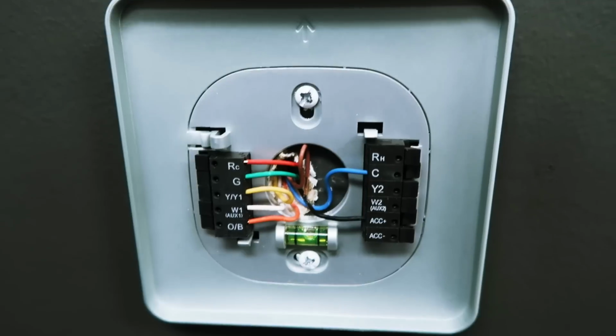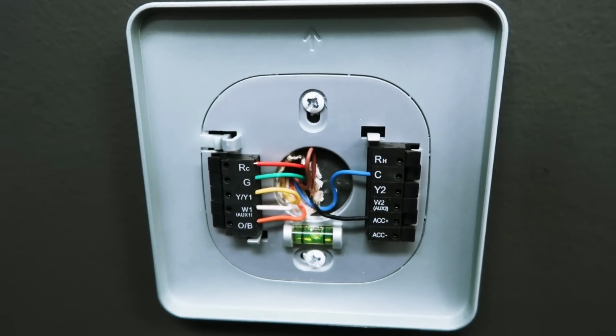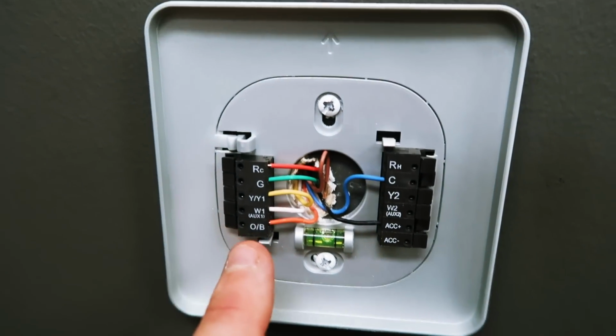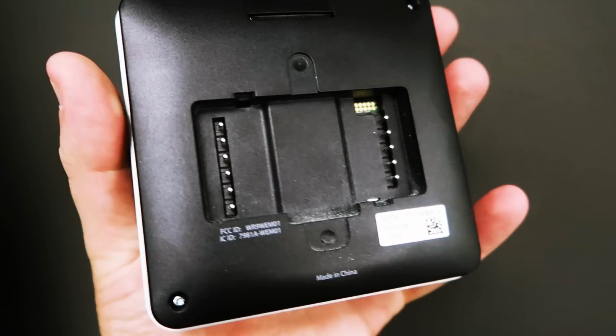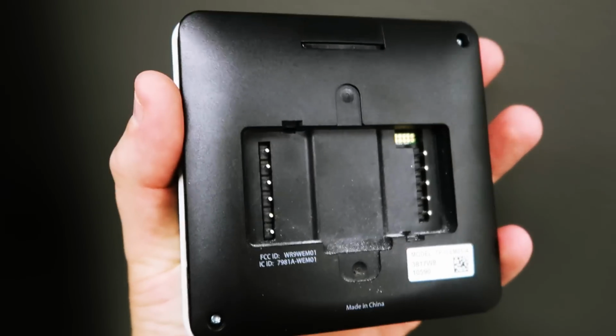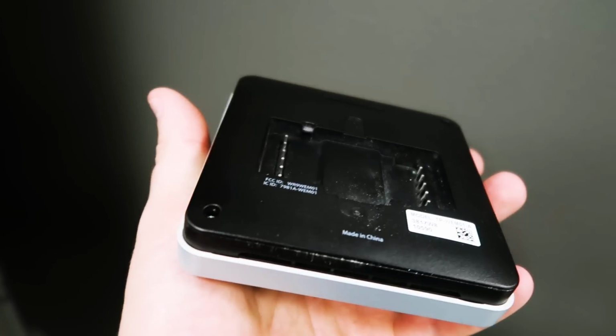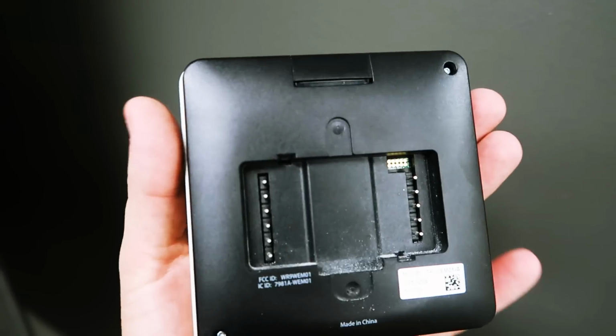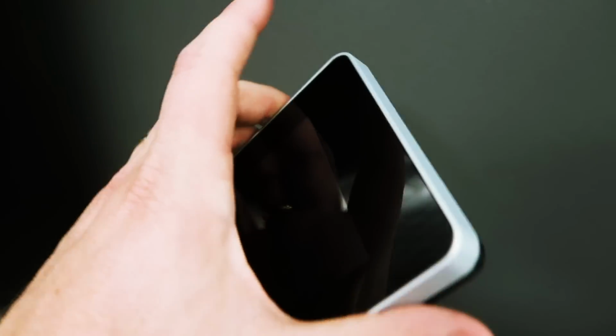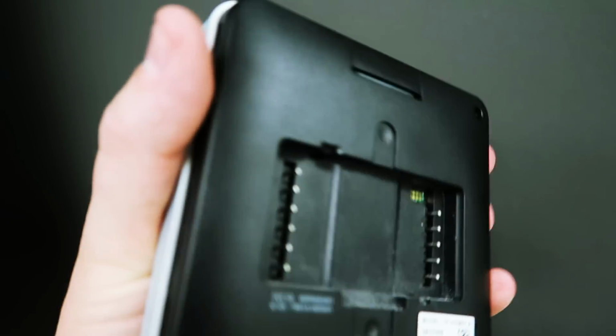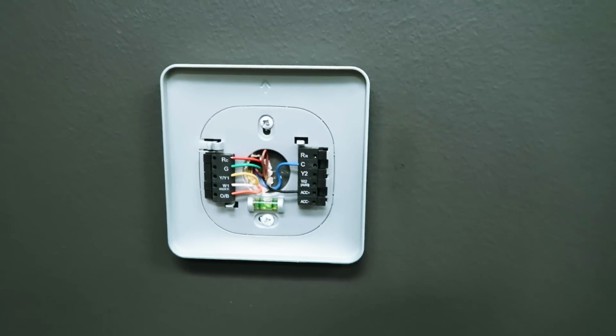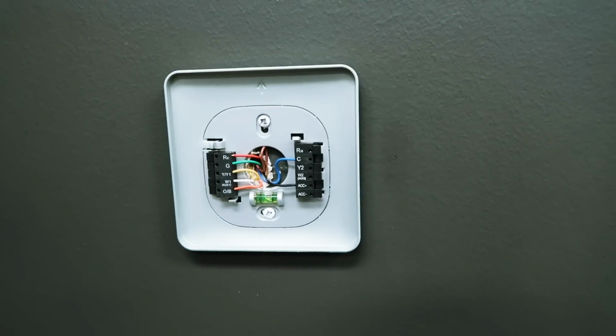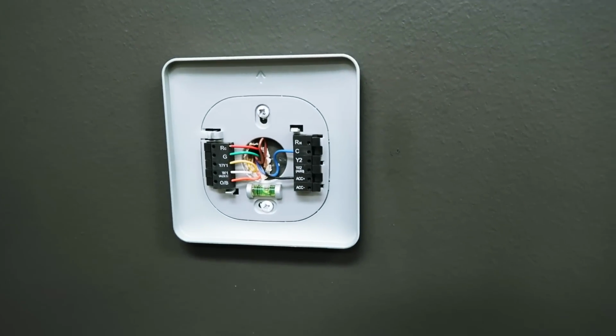I mean, this is my working hypothesis. Until we replace the thermostat, I'm not going to know 100%, but that's my working hypothesis, that I damaged the circuit in here to the extent that for some reason within the thermostat, that circuit is now generating additional heat, which the thermostat's picking up. So it's acting like additional resistance, or however you want to say that, that is causing additional heat in the thermostat that's driving the temperature up. So we're going to replace this thermostat. I hope we have another COR laying around here somewhere. We're going to replace it and see if the problem goes away, I should say.